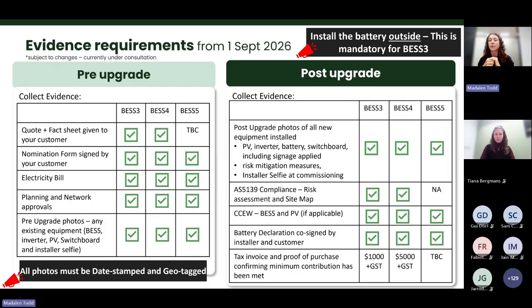Also for BESS 4 and 5, just be aware that the battery can be installed inside. That's totally fine, but you do need a photo of a compliant smoke alarm installed with it, and ensure it meets any specific clearance requirements from AS5139. This would actually be an example of a risk mitigation photo you might take for a fire hazard, so that's a nice example to include.